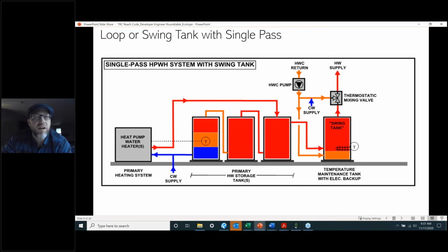Here's a bigger schematic, very similar to what Brian showed. We've got our heat pump water heating plant over to the left. We've got our primary storage, a swing tank, our hot water circ return, and our thermostatic mixing valve. What we're showing here is the cold water comes into this first tank. I like to use 3 tanks for primary storage, mostly because you can get your thermal well sensing right in the middle tank. This isn't shown in the right place. This gives you enough time to drain this tank, and once it cools down to about the midpoint, then you fire it and you get a good long heat pump run. That's been a really popular, successful design for us in Seattle. And then the swing tank is over here to deal with the hot water circ.